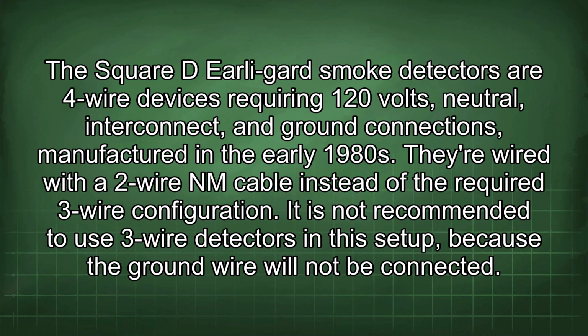The Square D Earli-gard smoke detectors are 4-wire devices requiring 120 volts, neutral, interconnect, and ground connections, manufactured in the early 1980s. They are wired with a 2-wire NM cable instead of the required 3-wire configuration. It is not recommended to use 3-wire detectors in this setup because the ground wire will not be connected.